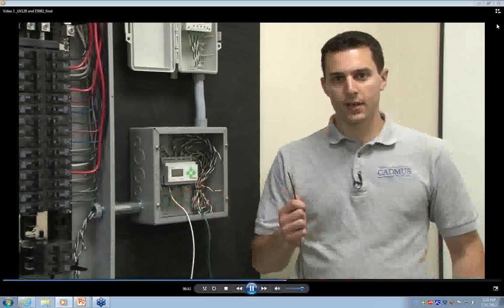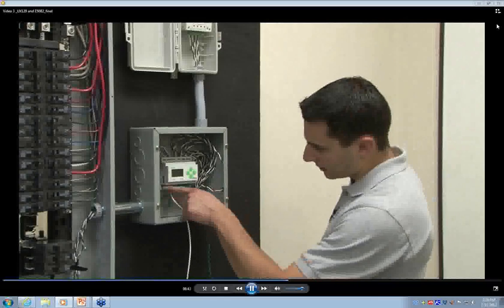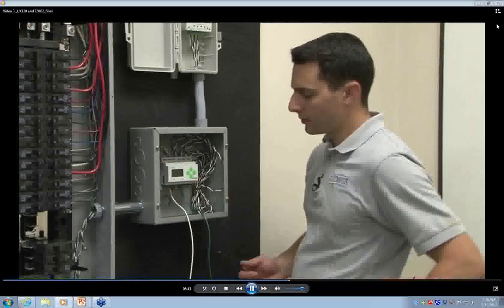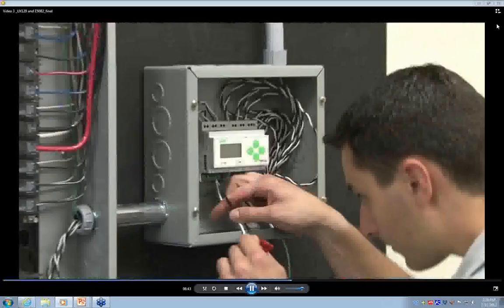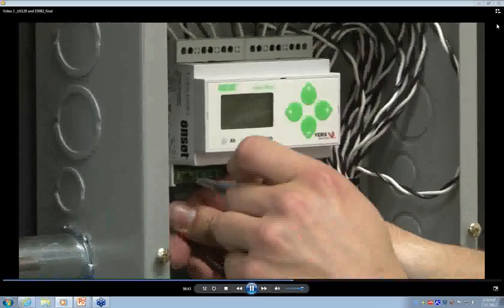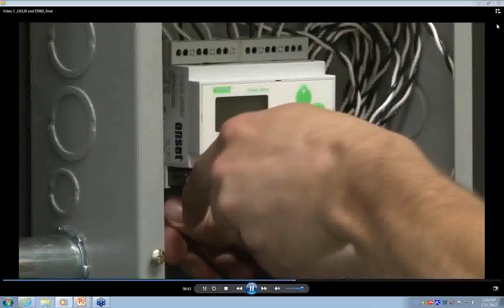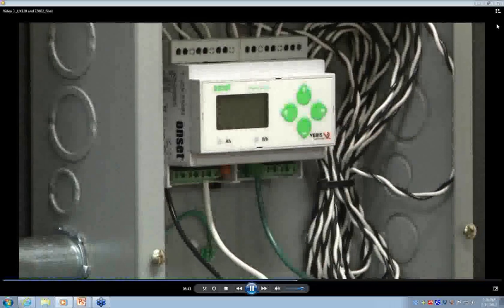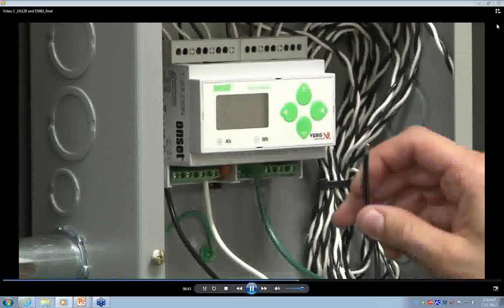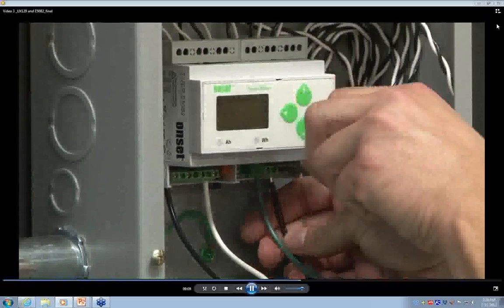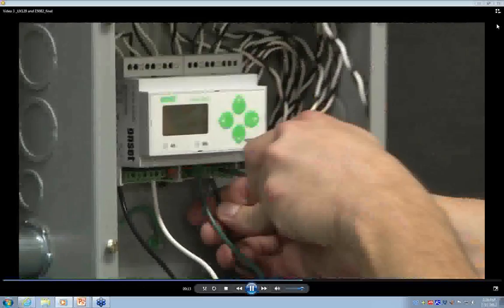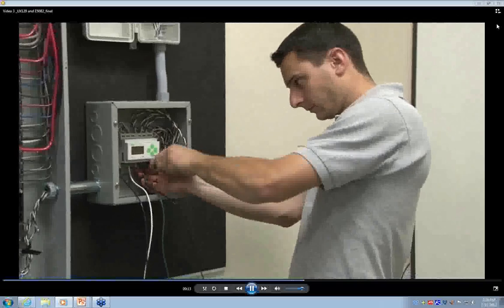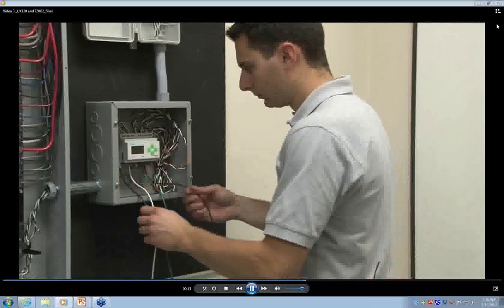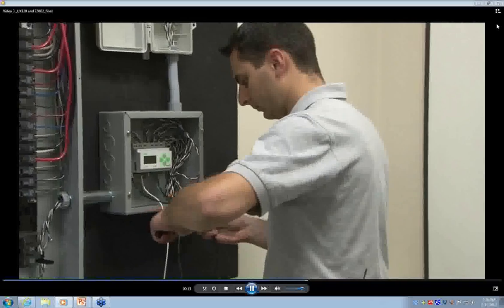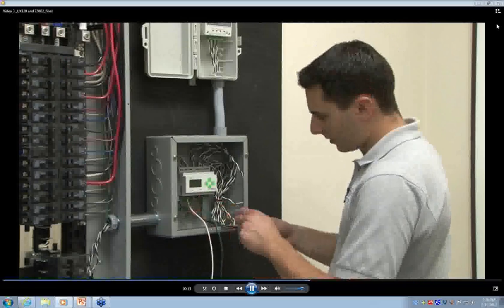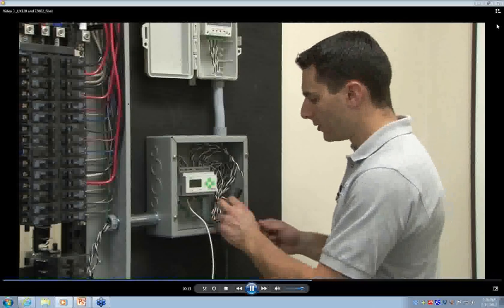We will now connect our black phase A terminal conductor to the far left phase A terminal as well as terminal number 1 in our control power terminal block. So we bring the black phase A conductor together with the terminal 1 conductor on the control power using a listed terminal.